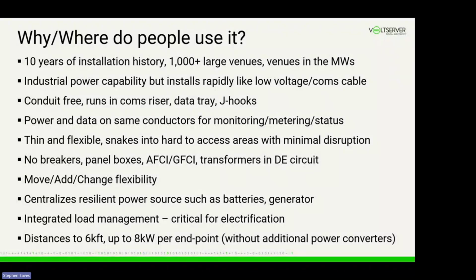Whatever practices you might use for low voltage or Ethernet cables, the same practice applies for this technology. It uses very thin cabling. The reason is because it's a high voltage distribution technology. So the innovation wasn't so much getting a lot of power into thin lines - that's already achieved by using high voltage, as anybody could see by looking out their window at the utility poles. The innovation was to make that safe.